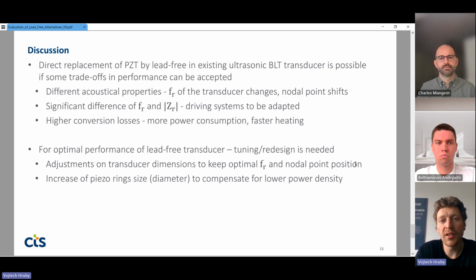It is important to mention that in this study, we didn't optimize the lead-free transducers. For optimal performance, tuning and redesign are needed. This means, in general, adjustments of transducer dimensions to keep the optimal resonance frequency and also the optimal nodal point position. An increase of piezo ring size, mainly diameter, might also be required to compensate for the lower power density of lead-free materials.